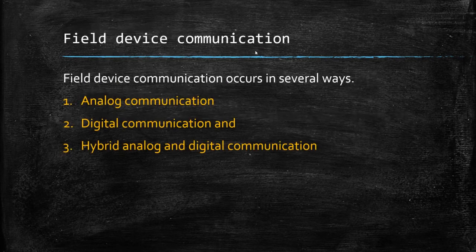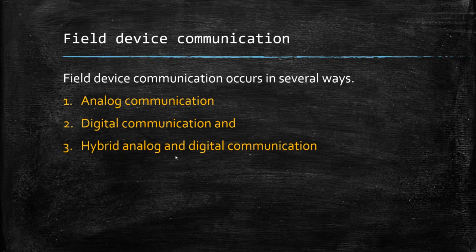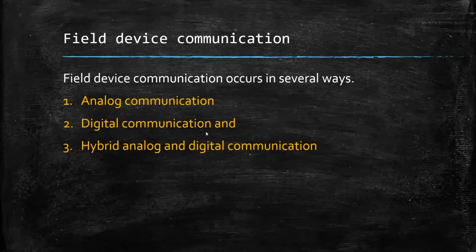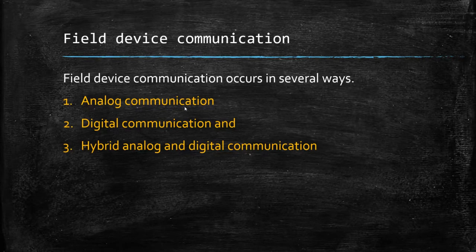Starting out with field device communication, since this is a communications course, we can identify that field device communication can occur in several different ways. We started out with analog communication back in the day, and this has evolved to digital communication today. We also have some that are a mixture — hybrid analog and digital. HART-type devices fall in here, where they have some components of an analog device and some components of a digital device. When addressing with HART, if you're using an address, it becomes digital; if you have an address of zero, it's analog.